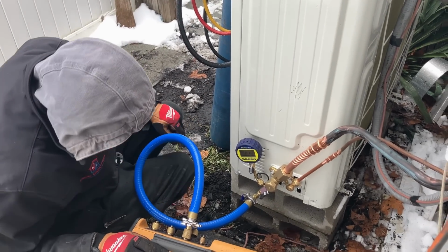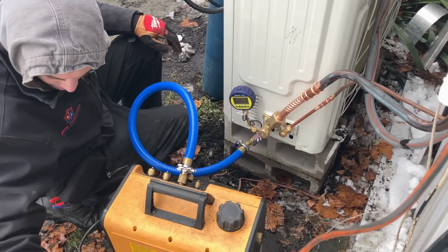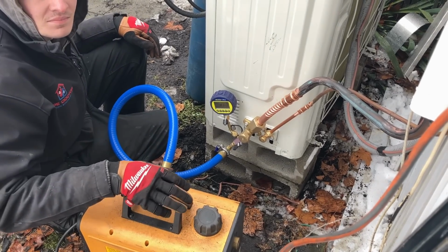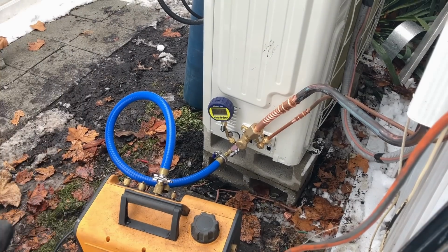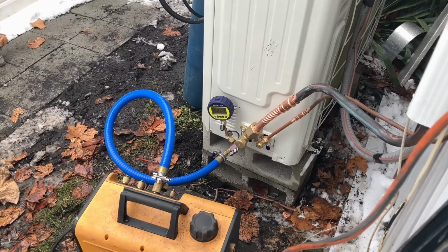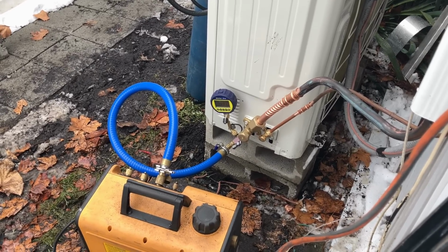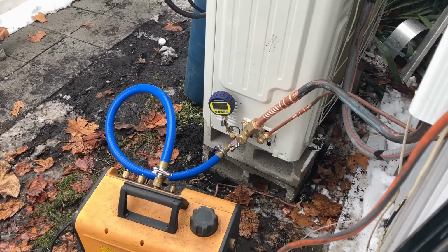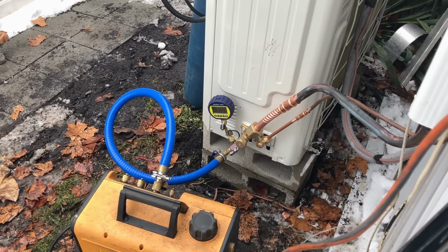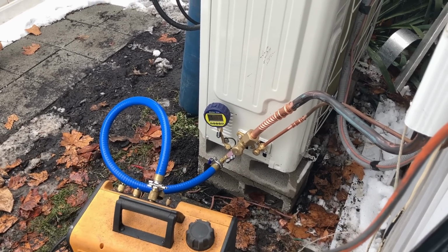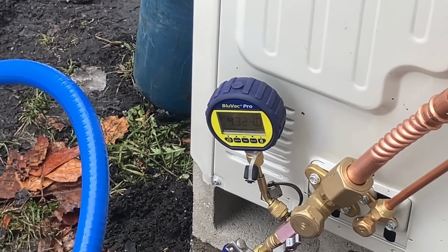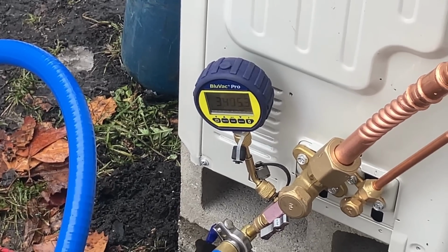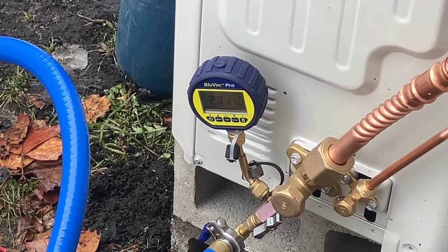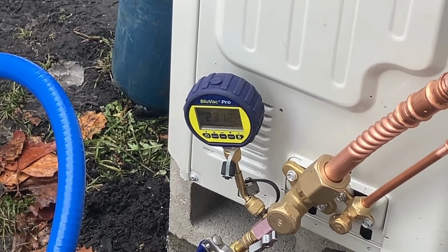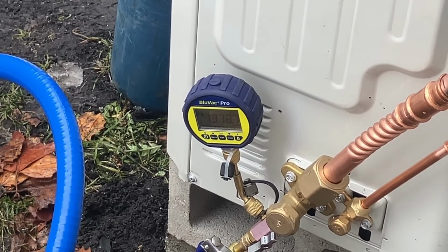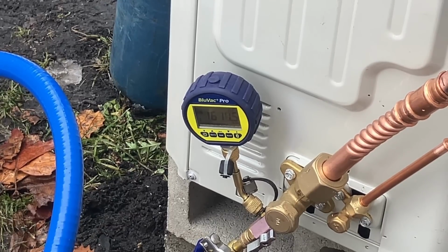Uncut, unedited, raw. You're welcome, Senville. Now, one of the great things about using the right tools for the job is that it allows us to do our job more efficiently and more effectively. If you're using your manifold to vacuum down, you're not going to be at 10,000 microns like we are already. 8,000, 7,000, 6,000, 5,000. I think I'm BSing you. There it is right there. We're using the Blue Vac Plus Pro micron gauge. We're at 2,700 microns, 2,400 microns, 2,000 microns, and dropping consistently.